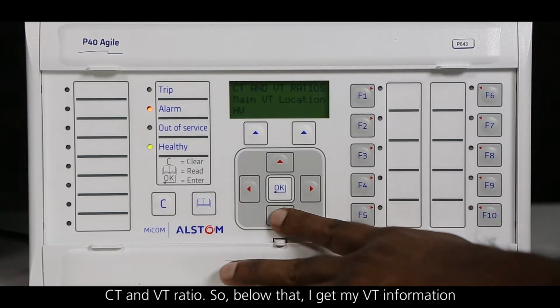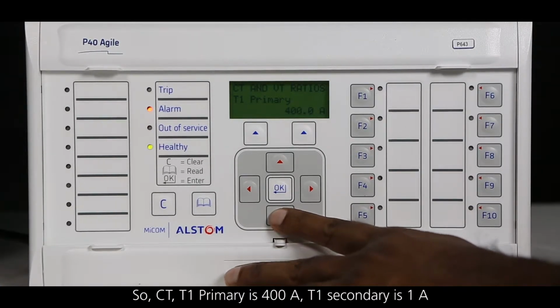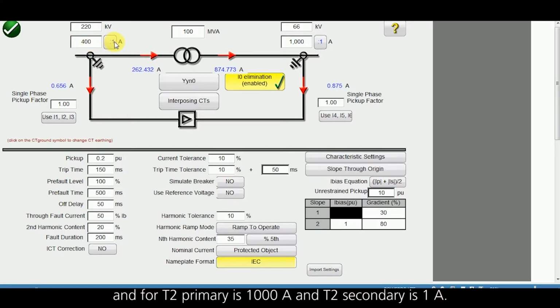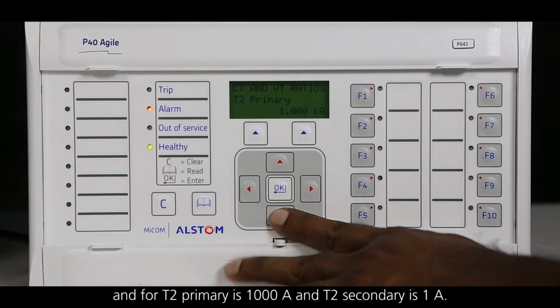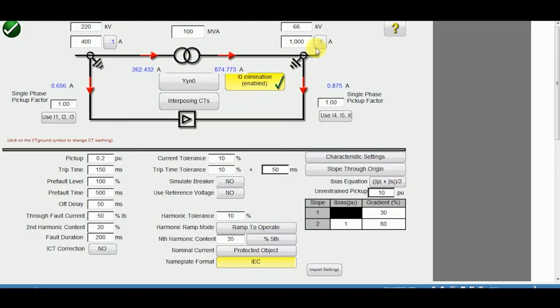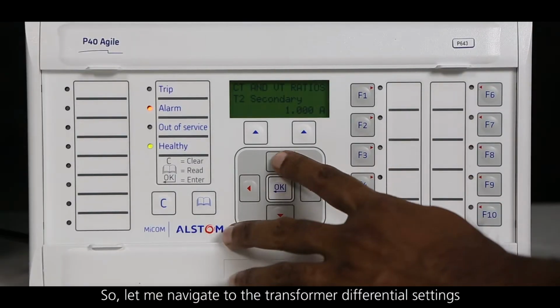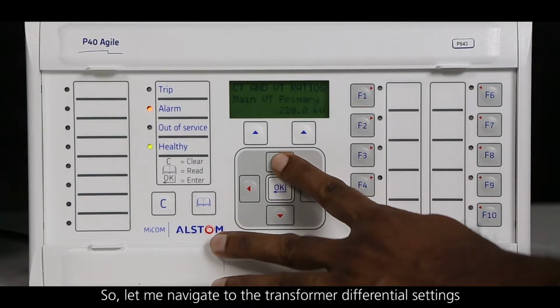CT and VT ratio. Below that I get my VT information. CT T1 is 400/1 amps, and for T2 it is 1000/1 amps, and my vector group is Yyn0 as seen earlier. Now below this line I need to configure the transformer settings. So let me navigate to the transformer differential settings.